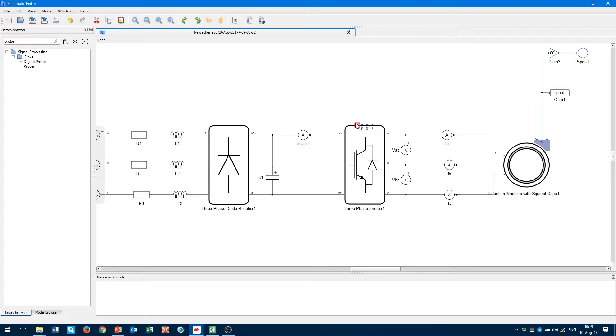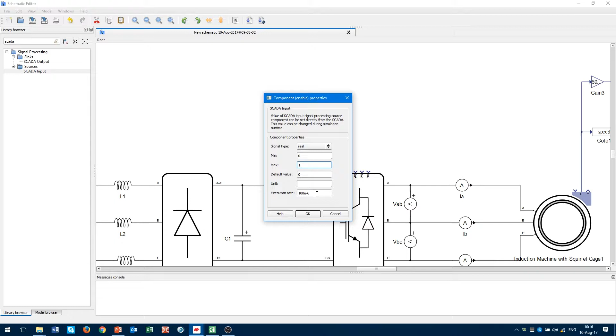In the property window, the minimum value we will set to 0 and the maximum value to 1. The execution rate will be defined as TS. Let's close this window. Now we will connect the SCADA input to the inverter input, and we will send the same value near the sum component with the goTo block.